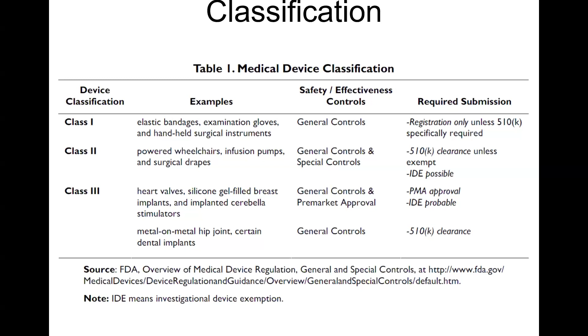Class 1 products need to adhere to the abbreviated quality system requirements and the ISO 13485 equivalents. They don't require what's called premarket notification; they simply have to identify what's called a device description under a classification of 21 CFR. There are about 2,000 plus medical device categories, so you still have to fit under an existing device description to be eligible for class 1 or class 2. For class 1, it's a self-declaration, and you have to be careful to make sure you truly meet the definition of that medical device category, and you're subject to annual registration and listing fees.